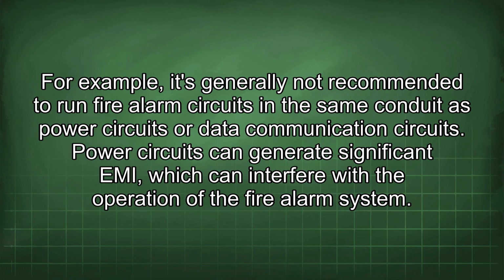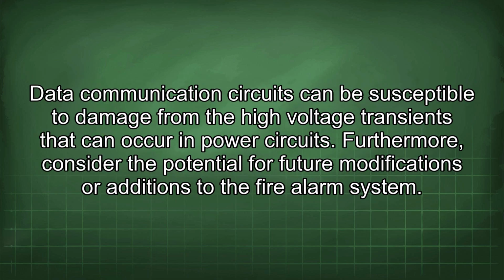Power circuits can generate significant EMI, which can interfere with the operation of the fire alarm system. Data communication circuits can be susceptible to damage from the high voltage transients that can occur in power circuits. Furthermore, consider the potential for future modifications or additions to the fire alarm system.